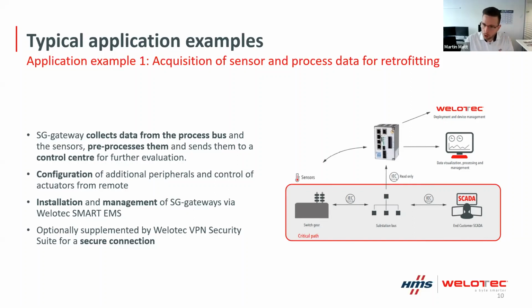If you put Welotec also in this place, it would even be possible to just hook up the SG gateway. The SG gateway automatically connects to the Welotec solution, automatically receives the fitting configuration from the Welotec server or from the SMART EMS system, and then the sensors can be connected. So in the end, it is possible to have a system fully installed without any manual programming or manual work - we let the machines do the hard part of the job. So this is what you can see in this first example.